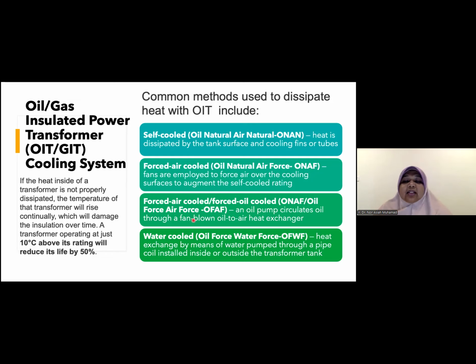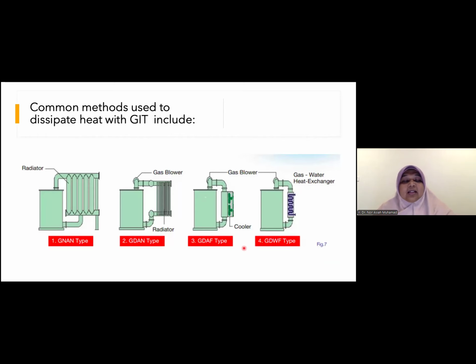So we also have oil natural, air forced, and oil forced, air forced transformers, where at the bottom of the transformer we have a pump that pumps the oil to circulate in the transformer, and also a fan blowing onto the fin. We also have the water cooled transformer, oil forced, water forced. This one adds water as a chiller to the transformer to make it cool faster. So this is the connection. This is the oil natural, air natural. This is the air forced. So we have the fan, and also we have the water exchanger.